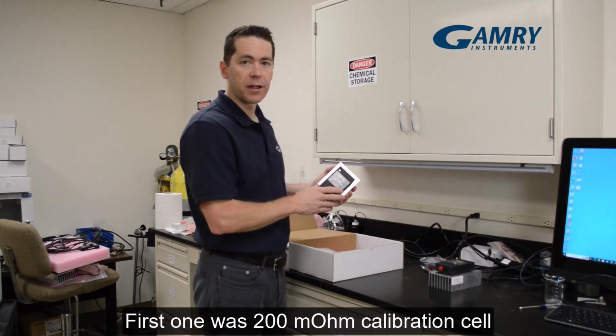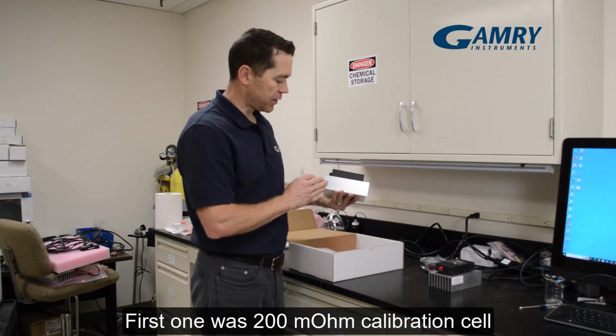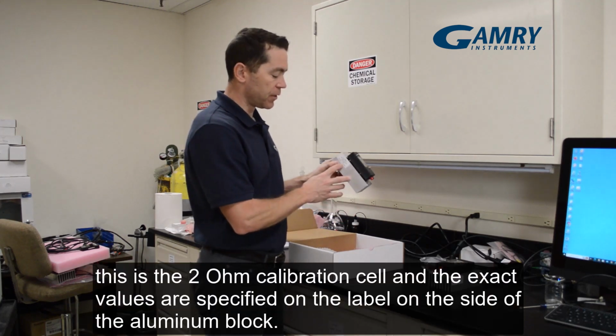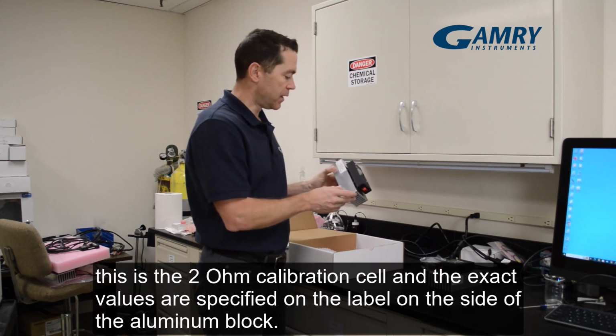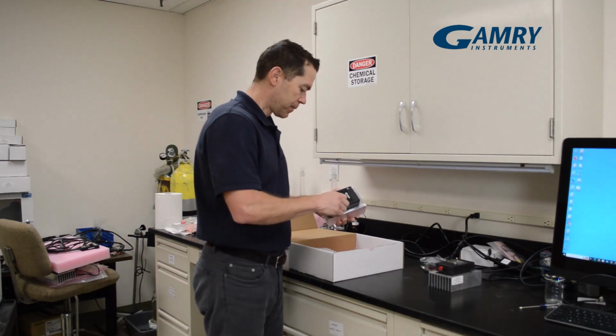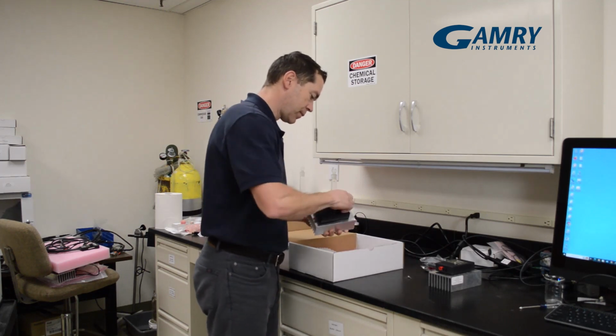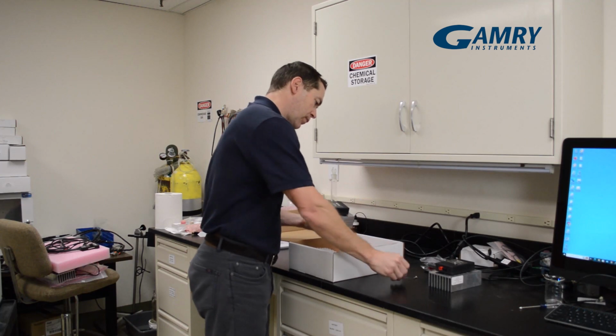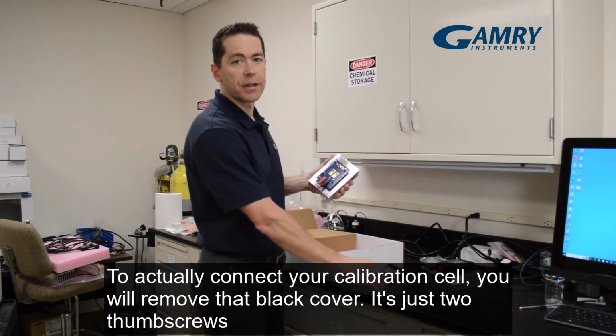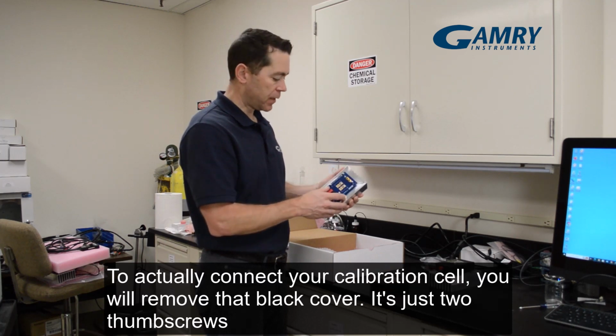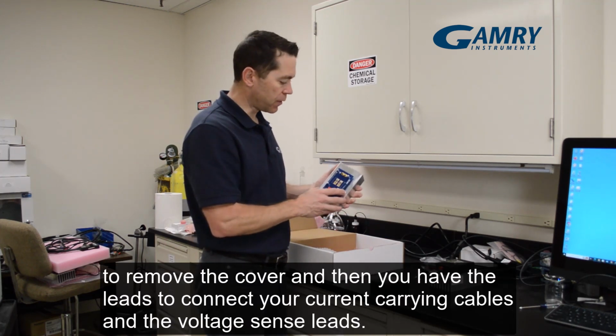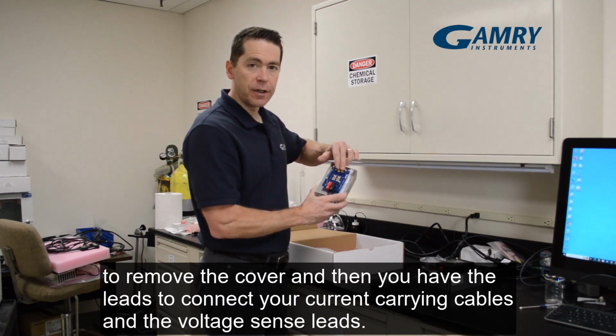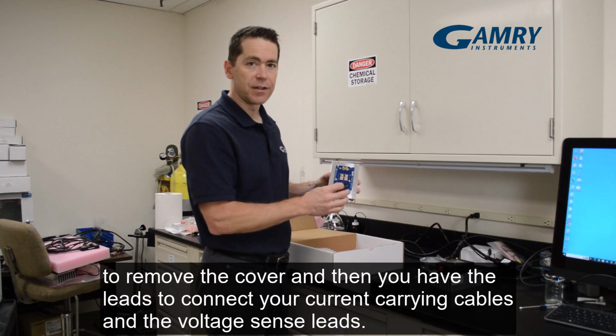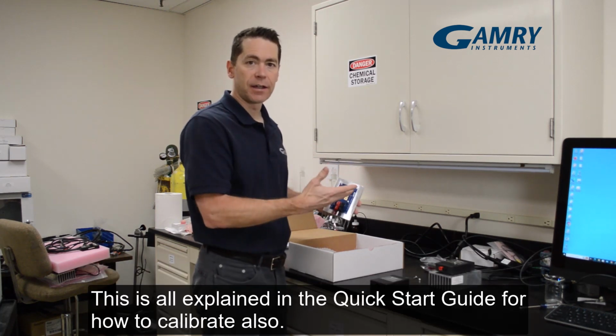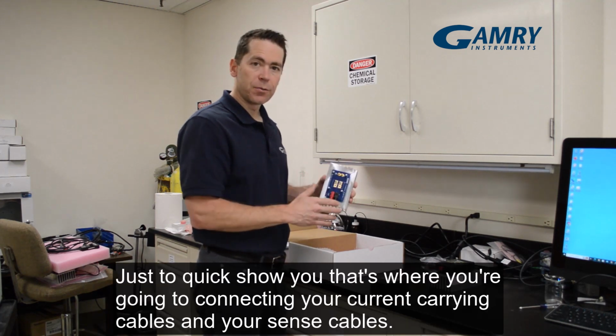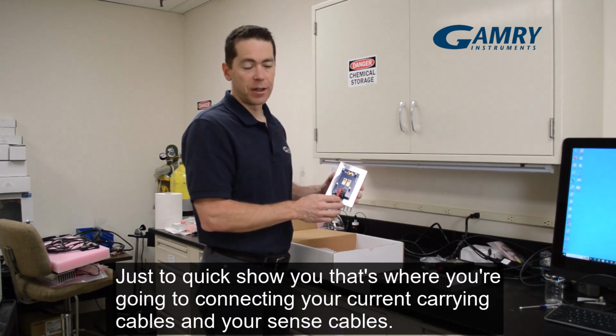So the first one was the 200 milliohm calibration cell. This is the 2 ohm calibration cell. And the exact values are specified on the label on the side of the aluminum block. To actually connect your calibration cell, you're going to remove that black cover. It's just two thumb screws that you unscrew to remove the cover, and then you have your leads to connect your current carrying cables, and then you also have your voltage sensing leads, and this is all explained in the quick start guide for how to calibrate also. But just to quickly show you, that's where you're going to be connecting your current carrying cables and your sense cables.